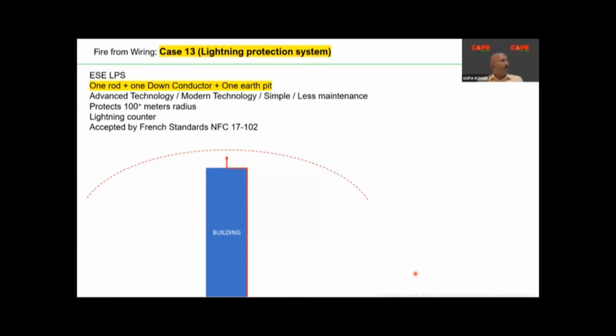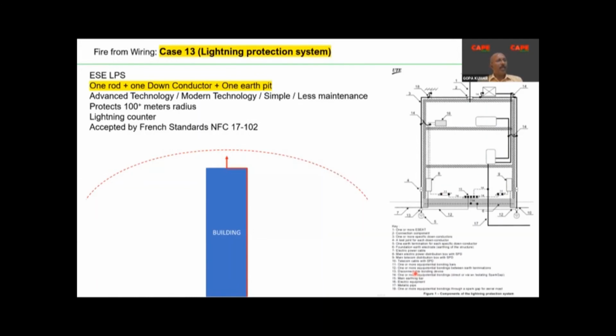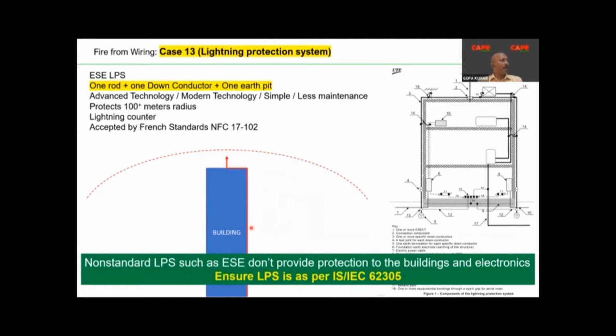People say that this is accepted as per the French standard, but be sure that the French standard is not accepted in the way it is taught in India. One rod, one down conductor, and one earthing could create, of course, fire, but it could also create a lot of failures in your electrical system. You must ensure that the lightning protection system is as per IS/IEC 62305 or the National Building Code, because in National Building Code Part 8 Section 2 we have included Chapter 11, a very good chapter where what you should do is very well compiled, and you can also refer to the National Building Code.